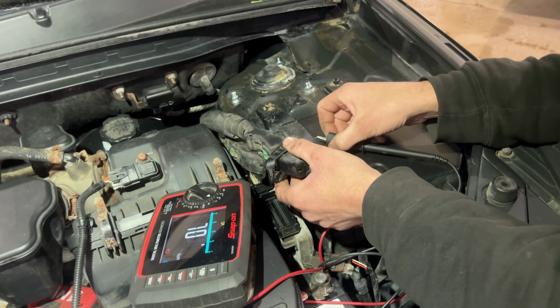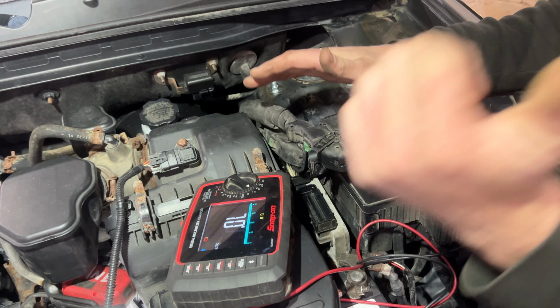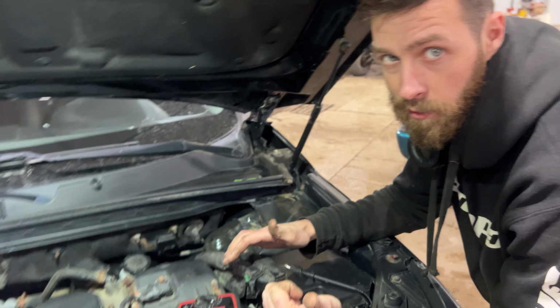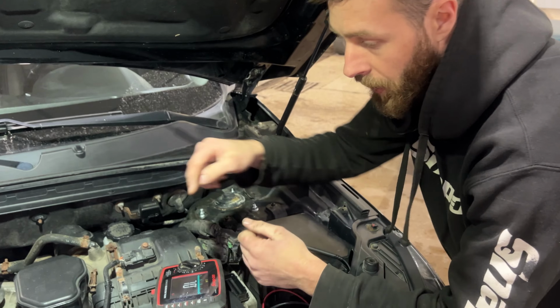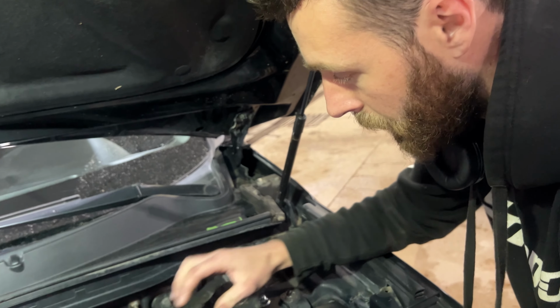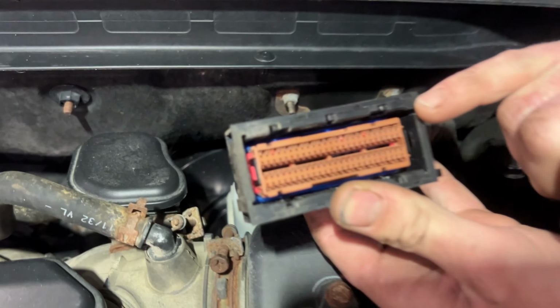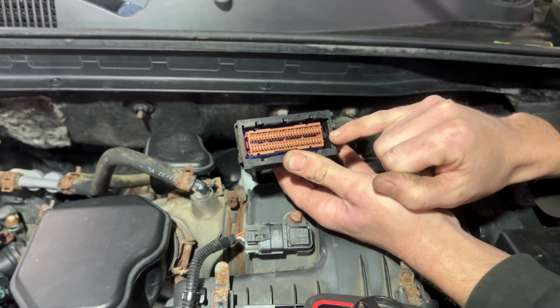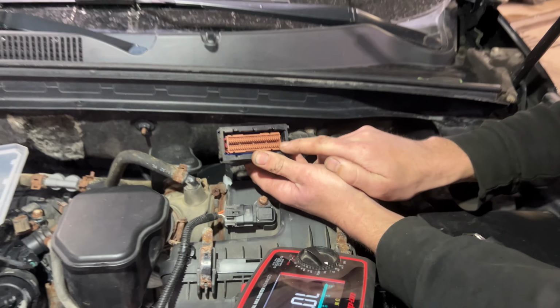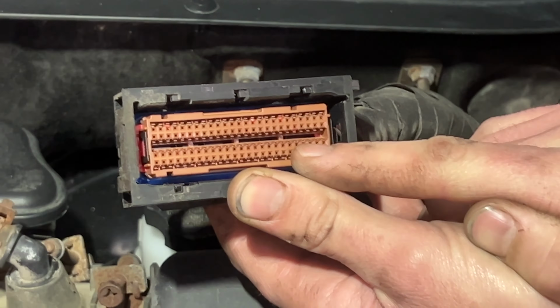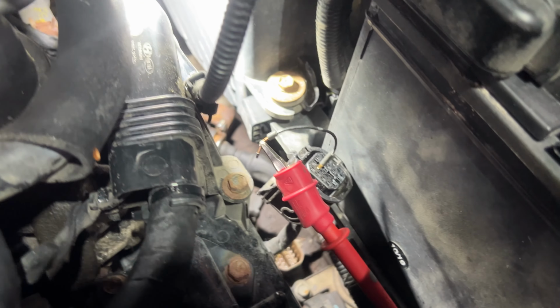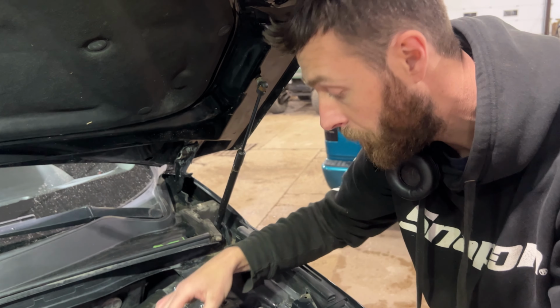So we just tested our wires. Like I say, the pinout on the instructions was wrong, they lied to us. Pin number 9 on the transmission connector, that's our sensor positive, that goes to pin 55 on the brown connector. When you're looking at it like this, it's row 1, 2, 3, the 3rd row down, and then you move over this way, so that would be 51, 2, 3, 4, 5. So it starts at 51. So 55 goes to pin number 9, and then 57 goes to pin number 13. So it was just this brown connector that they messed up.